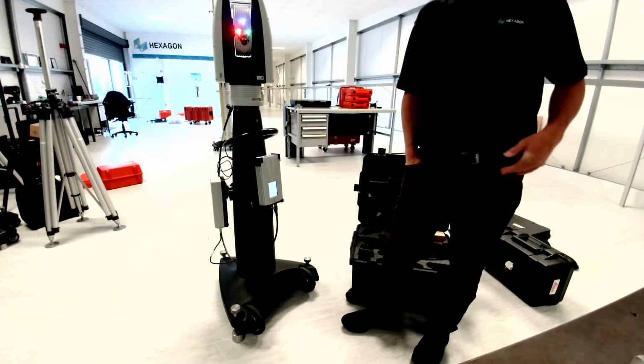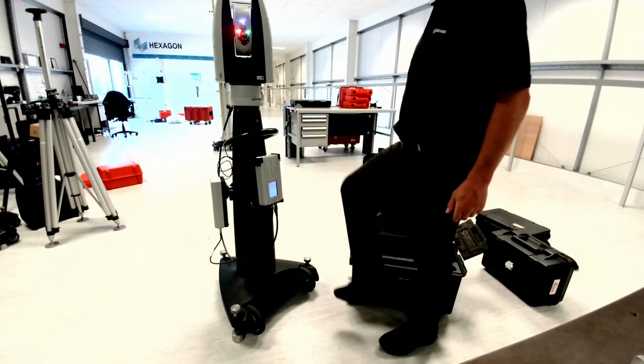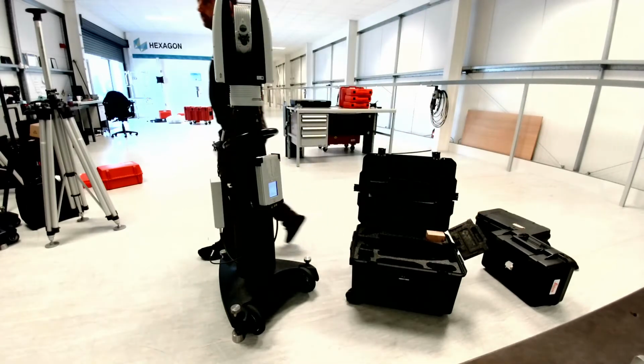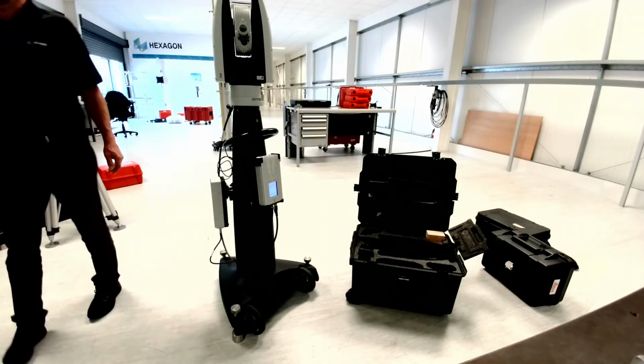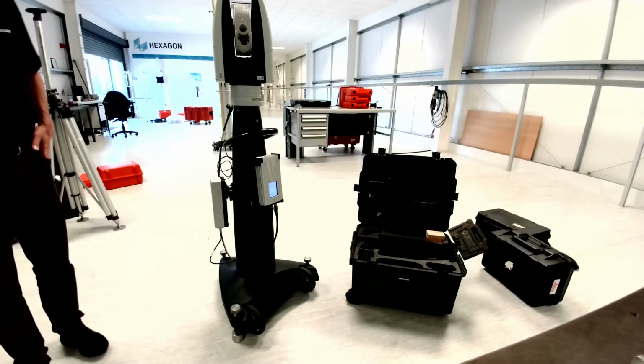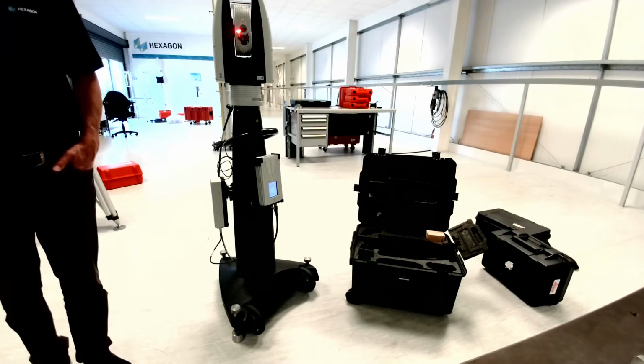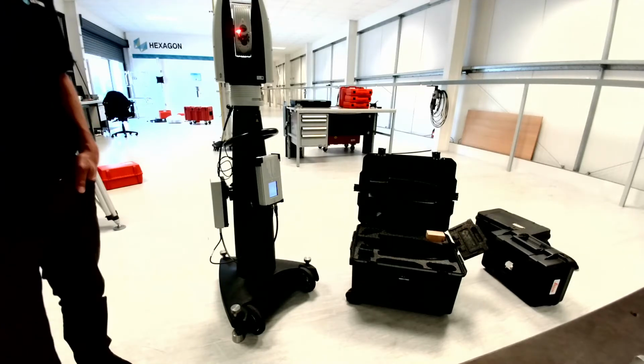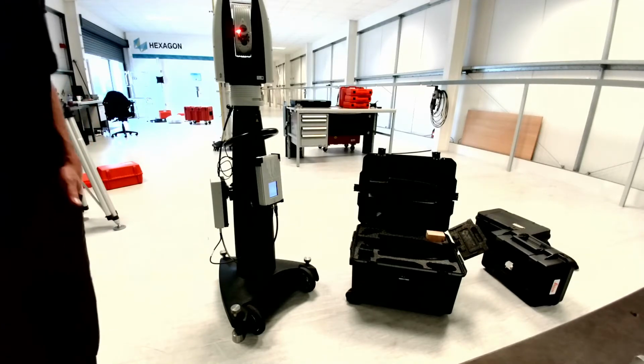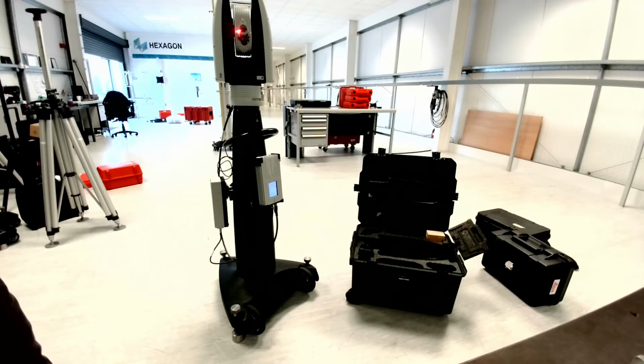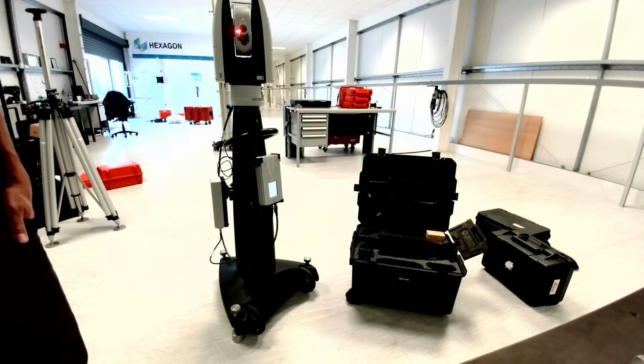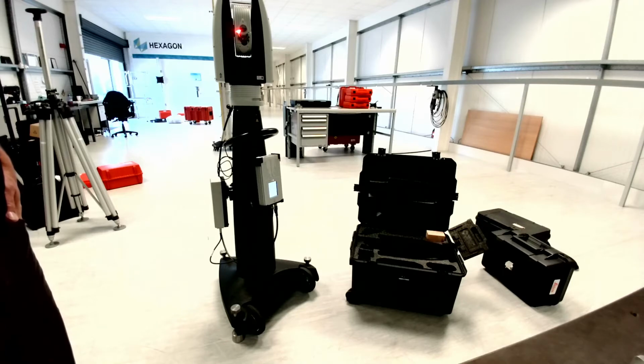In regards to the warm-up period, I think it's about 5 minutes maximum, but it depends how warm the tracker is and what the ambient temperature is - maybe 2 to 5 minutes. You can see the laser flashing, which gives you an indication of how close to warmed up the tracker is. The longer the red flash, the closer it is to warm up. The controller's just booting up now.